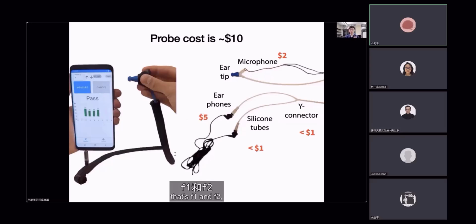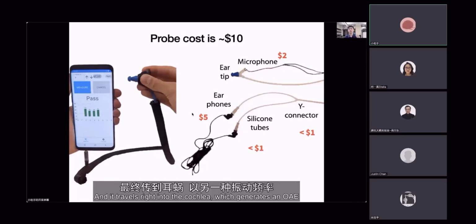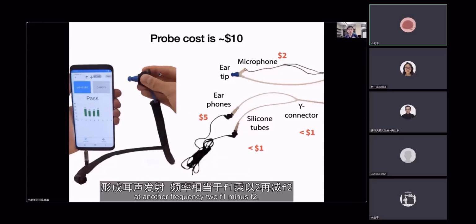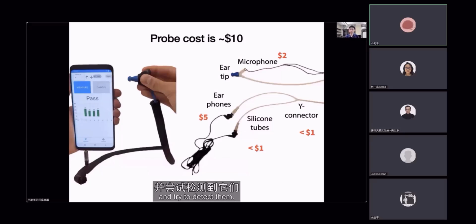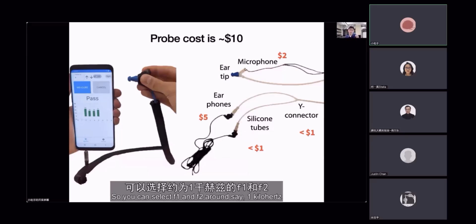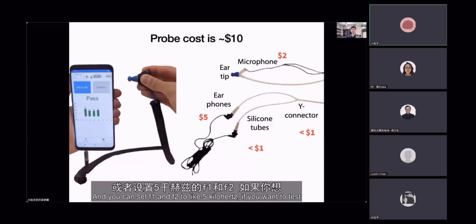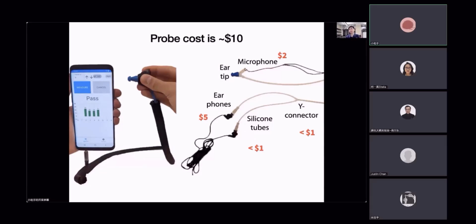Now, in order to actually elicit OAEs with our test, we just have to send two tones through these two earphones, F1 and F2, F1 through the left earphone and F2 through the right earphone. The tones travel along these silicone tubes out through the ear tip, and travel right into the cochlea, which generates an OAE at another frequency, 2F1 minus F2. And then the microphone can actually listen to these OAEs and try to detect them. You can actually test at multiple frequencies here. So you can select F1 and F2 around, say, 1 kilohertz to test hearing at that range.